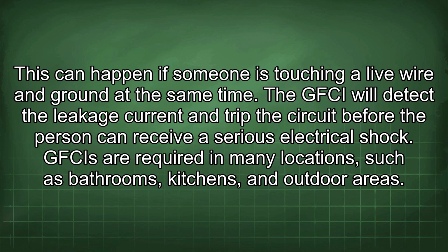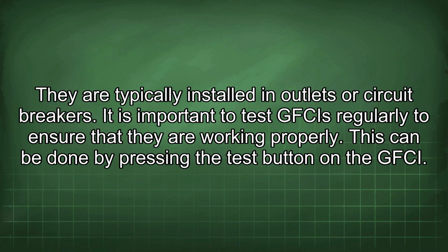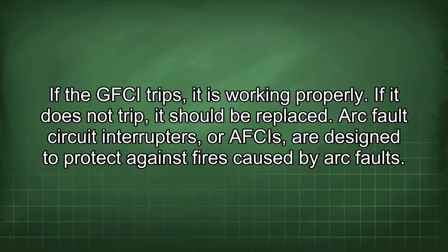GFCIs are required in many locations such as bathrooms, kitchens, and outdoor areas. They are typically installed in outlets or circuit breakers. It is important to test GFCIs regularly to ensure that they are working properly. This can be done by pressing the test button on the GFCI. If the GFCI trips, it is working properly. If it does not trip, it should be replaced.